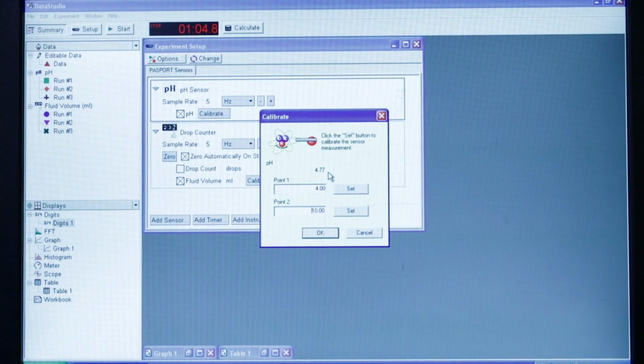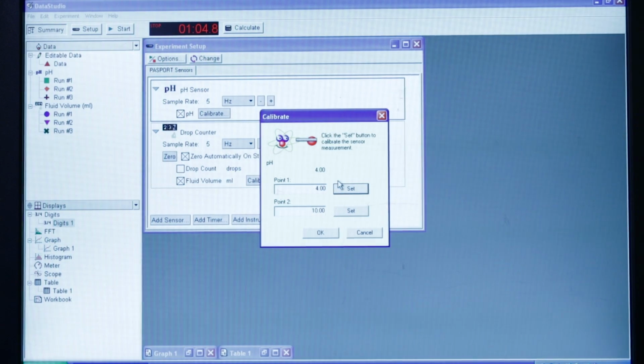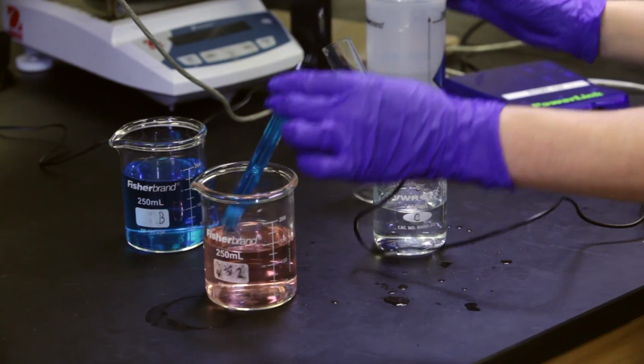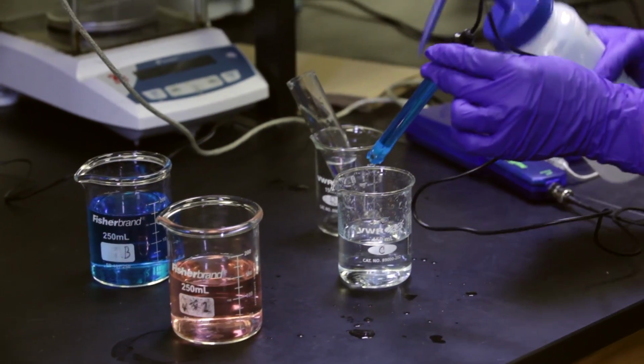So right now it's reading about 4.77, but it needs to be 4. This is a standardized solution. It is pH 4, so I'm going to set that standard. And then I'm going to go back to my probe. I'm going to rinse it off.